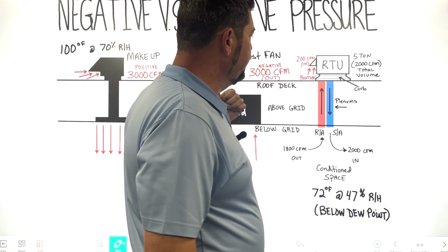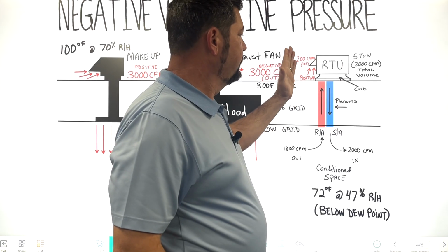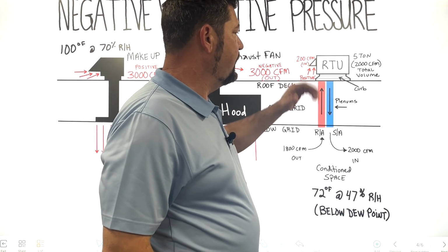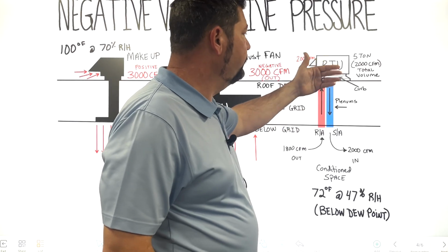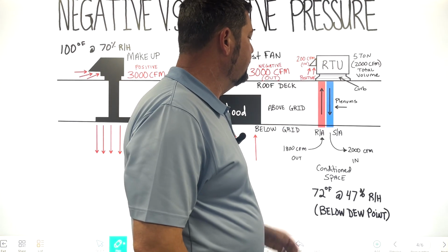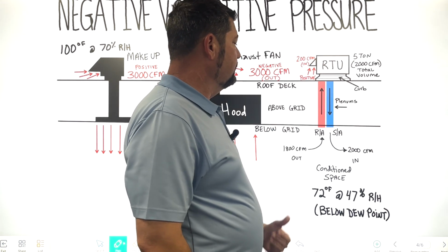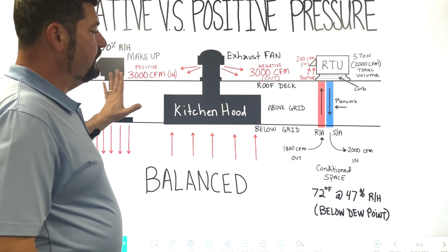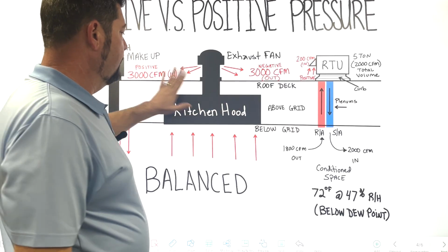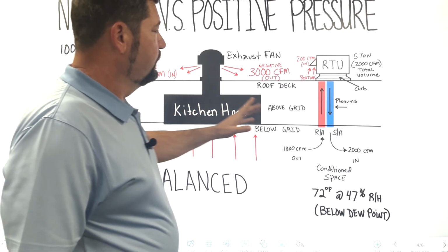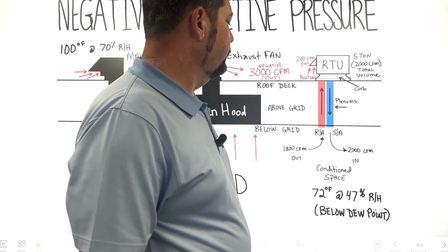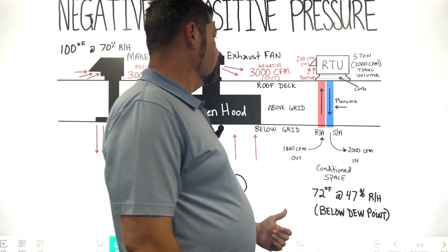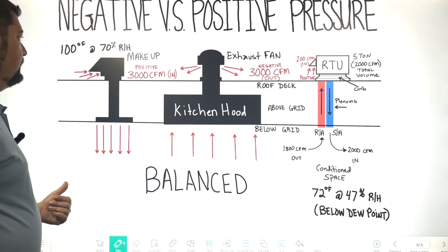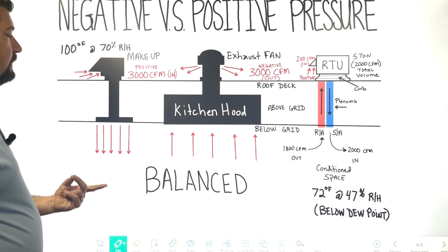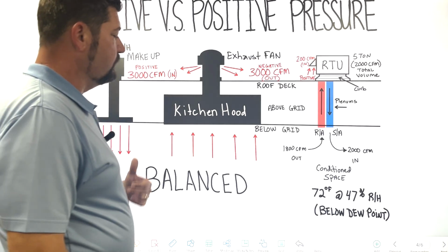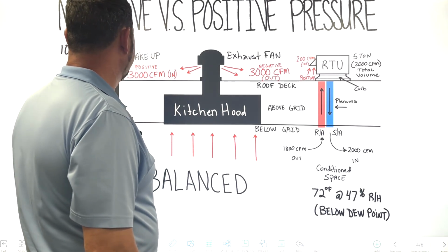The RTU, just like we had on the previous screen, is going to typically have a fresh air on it. And if it does not have a fresh air on it because maybe the RTU was replaced and they forgot to put a fresh air on it, if you're in that situation, then your hoods can be off. You could be in a building where these aren't even on at the time, or maybe they're not even present, and your problem's just simply the RTU. So humidity is always going to be a concern in the event that the humidity and the temperatures are very close in range, where you are at that dew point to where things are going to sweat.